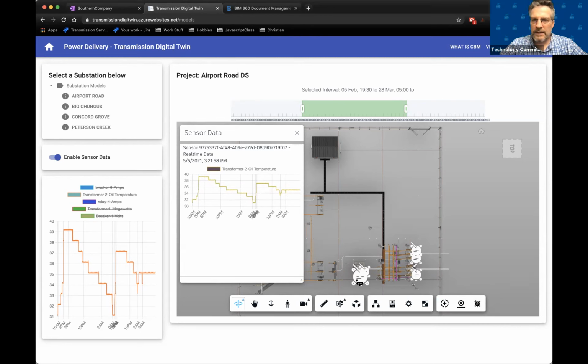So if it's indicating it needs service, can I get equipment into the substation to do maintenance on it? Like if I need to lift that transformer up with a crane or something, do I have enough clearance inside my substation to do that?